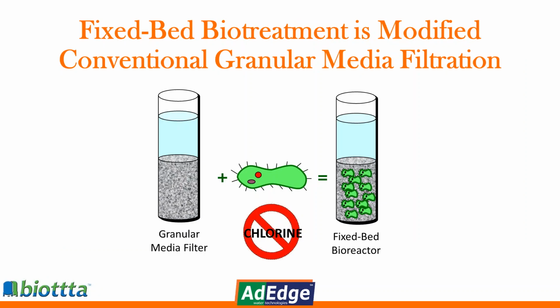So here's a little rendition. Again, we're going to have two pressure vessels. We're going to use a granular filtration media inside there, which is activated carbon. We take that activated carbon and add some nutrients. We don't want to see chlorine in our system, though we will be testing chlorinated water through our system down at the San Diego Trail site, so it'll be interesting to see how our system reacts to that. Ultimately, you get the granular media, you get some nutrients in there, and you end up with a fixed bed bioreactor that has bacteria growing within the carbon, and the bacteria are then used to break down the contaminants.